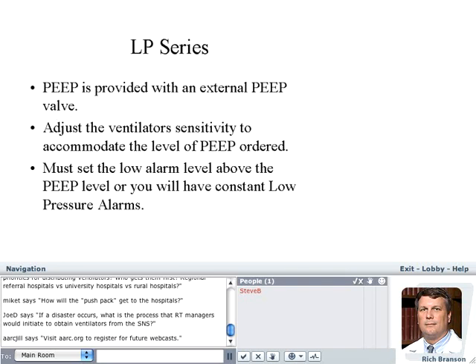With the LP series, you do get an external PEEP valve. And remember, this is like in the old days. The LP10 isn't capable of automatically knowing what the PEEP is and keeping the sensitivity the same. So you literally will put the PEEP valve on and then increase the sensitivity, make it more sensitive with the sensitivity setting until you see it start to auto-trigger. And then when you see it start to auto-trigger, then you'll turn it back to the lowest sensitivity setting that allows the patient to trigger to the ventilator, but precludes auto-triggering.